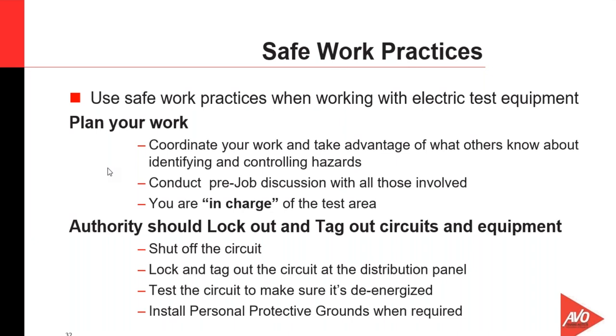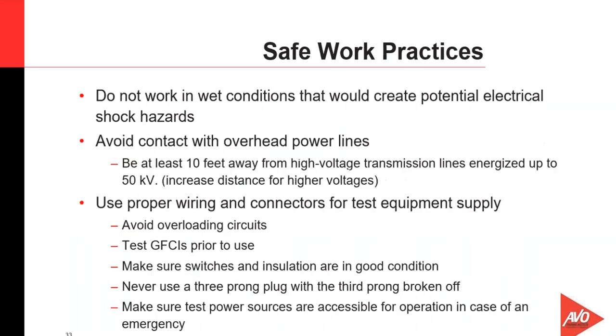It's not a good idea to operate high voltage test equipment in extreme wet conditions. So we need to make sure that we can control the work area, control the environment as much as we can in the work area, so that we're not operating equipment in areas where we're inundated with water. Avoid contact with other pieces of equipment or other lines or bus work or anything like that that's in the work area. We should do a survey of the test site to make sure that we understand what is energized and what is de-energized, and certainly the system that we're working on.